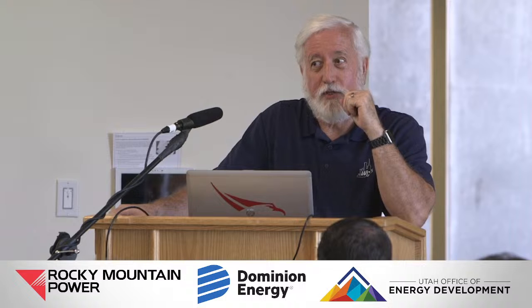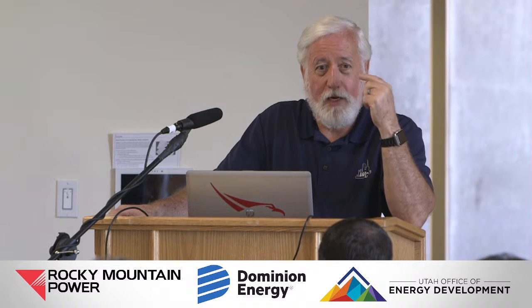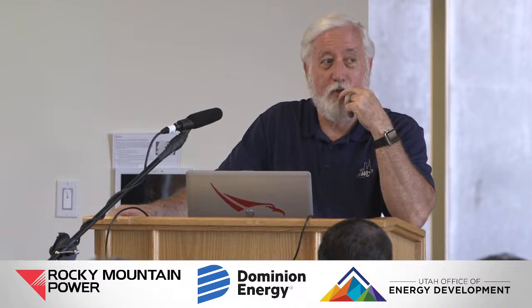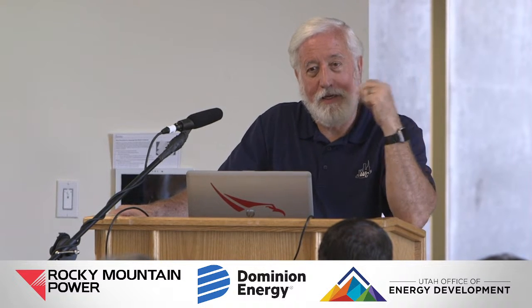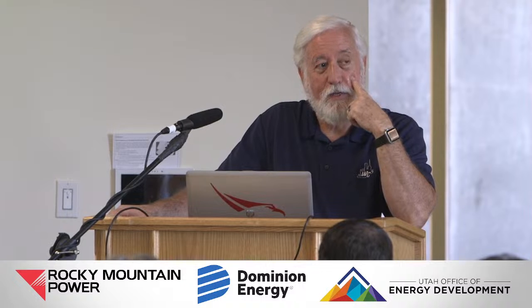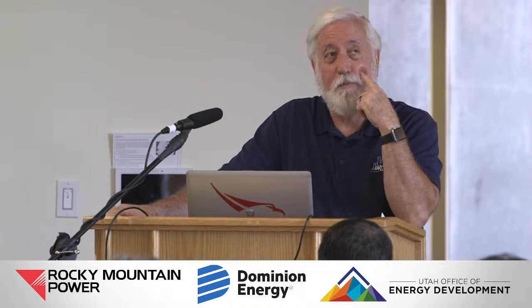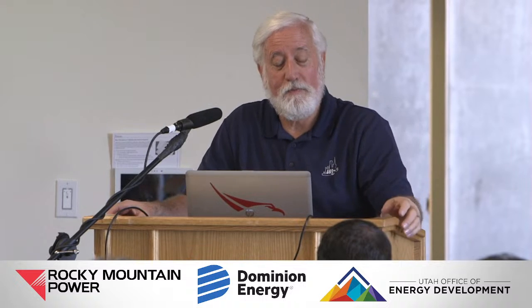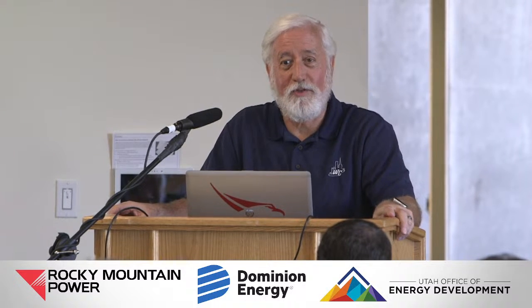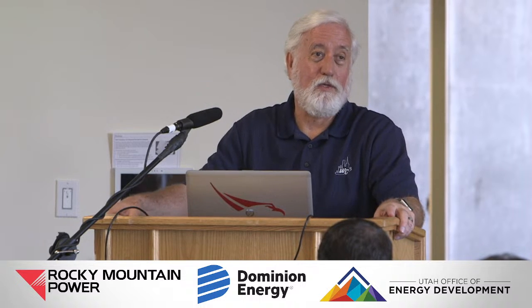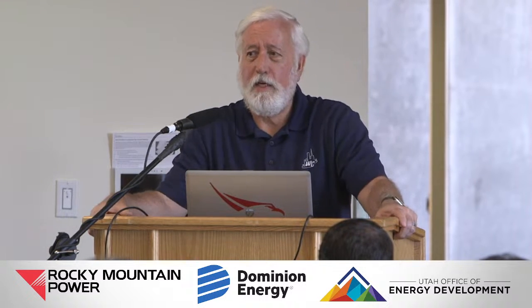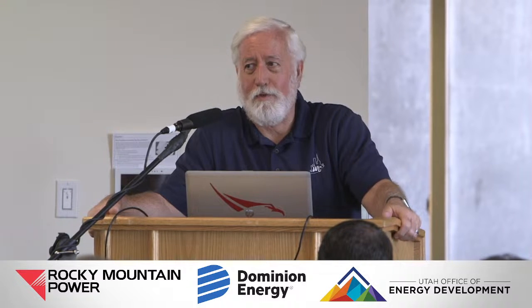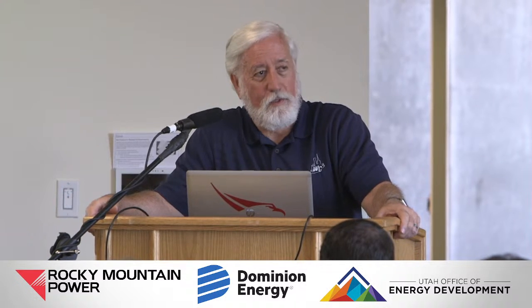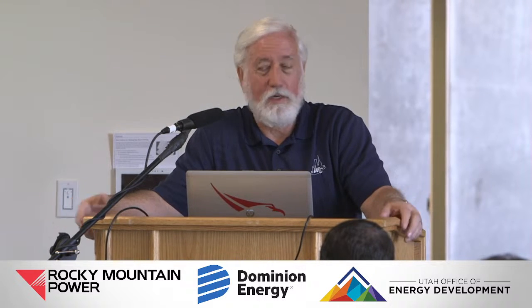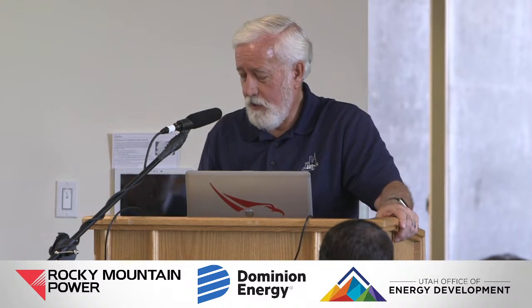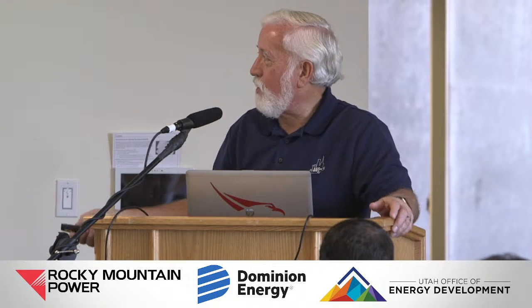As I read the IECC, all these apartment projects going up right now should have economizers because the total BTUs exceed the limit in the IECC. I asked ICC for an interpretation, and they said, well, yeah, I guess that's what it says. I think that's foolish because there's no way you can ever justify the cost of putting an economizer on a 1-ton or 1.5-ton system. You'll never produce enough savings in a residential unit for that to pay off.